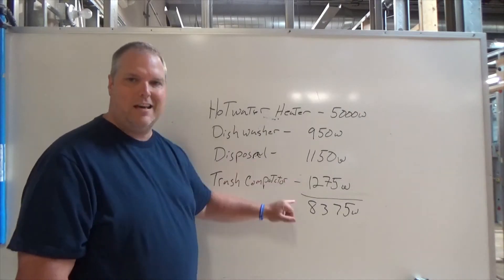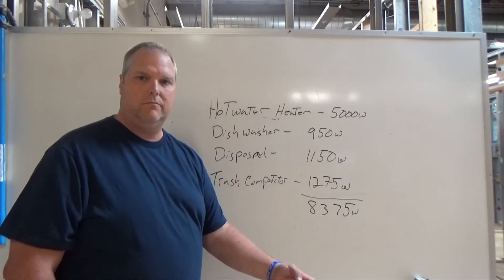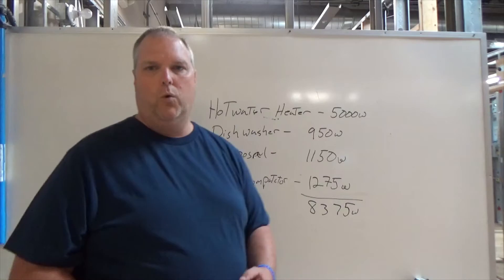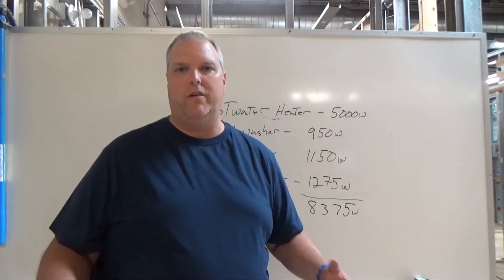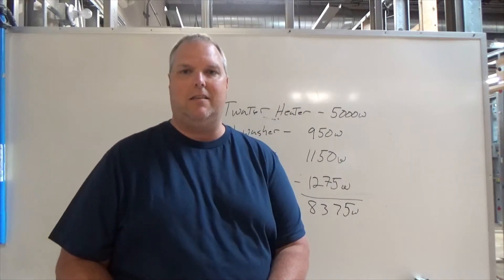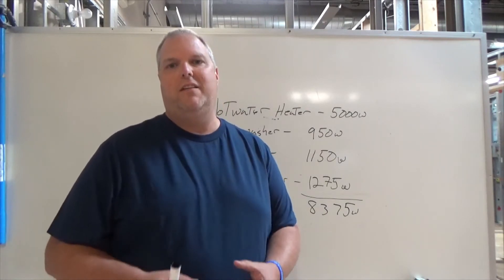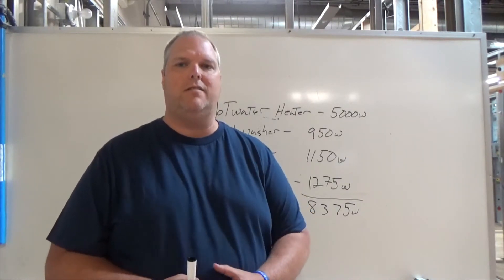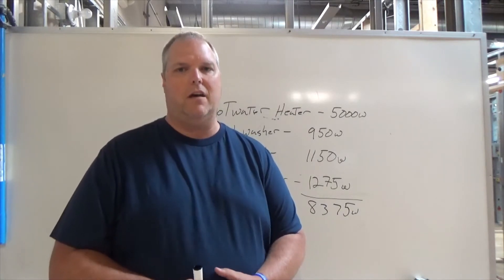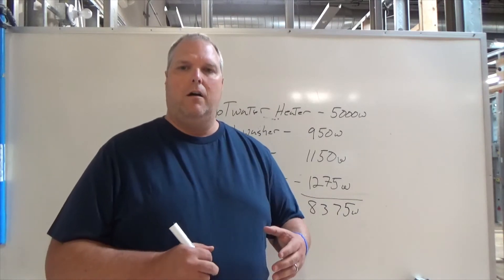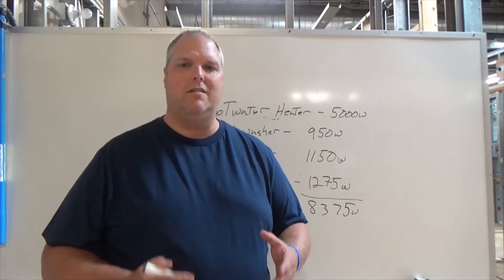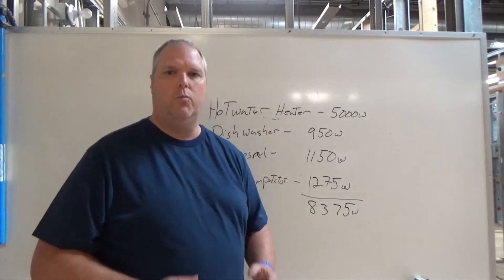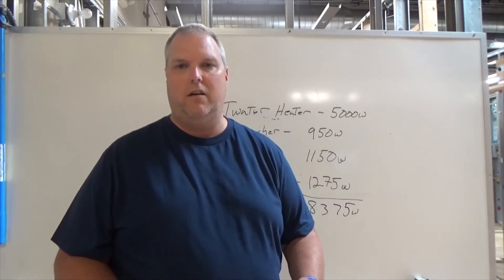We're taking all of these at 100 percent of their full load current. In the fixed appliances calculation at line 10, we multiply by 75 percent because we have more than four fixed appliances connected. That's taking all of them at 100 percent, but the demand factor for fixed appliances is applied at 75 percent. What we're really stressing is that for the standard calculation, all motors are sized at 100 percent — then we have to find the additional 25 percent for the largest motor.